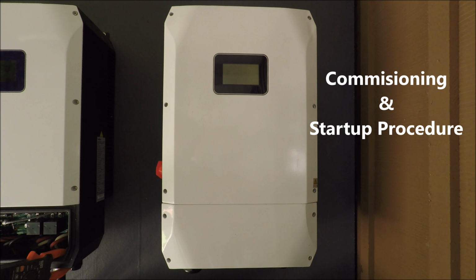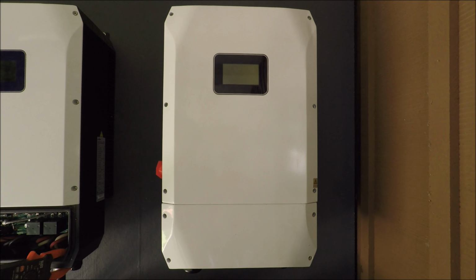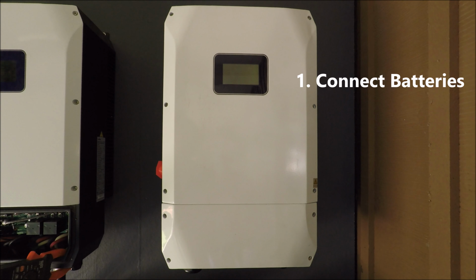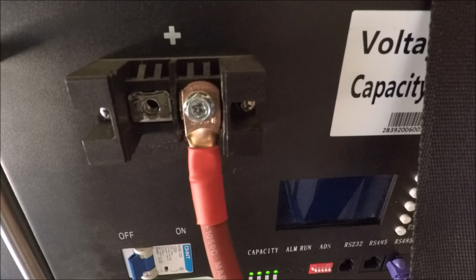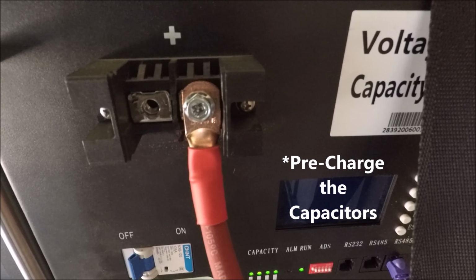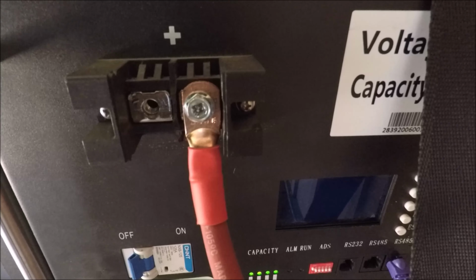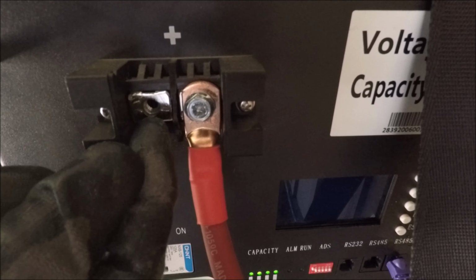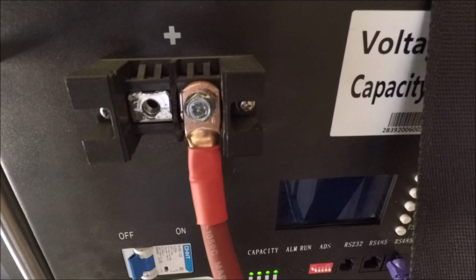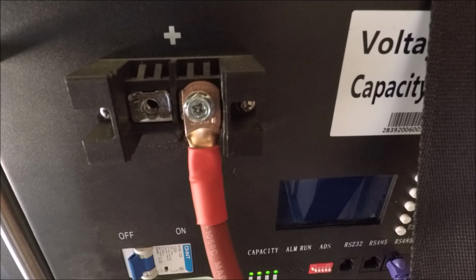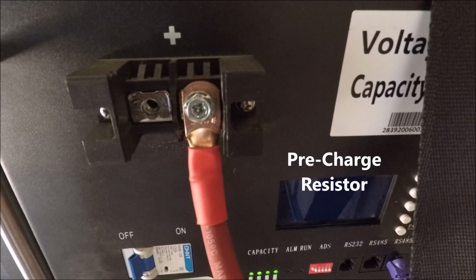For most inverters, there is a standard startup procedure, so we're going to go through that to get the inverter turned on. The first thing that you want to do is connect the batteries. Whenever connecting your batteries to your inverter, you always want to make sure that you pre-charge the capacitors in the inverter. This is very important because even small batteries can cause a large spark or an arc when you connect to the terminal here. So to prevent that arc, which can get very extreme to the point of sometimes even welding terminals together, you want to use a pre-charge resistor.